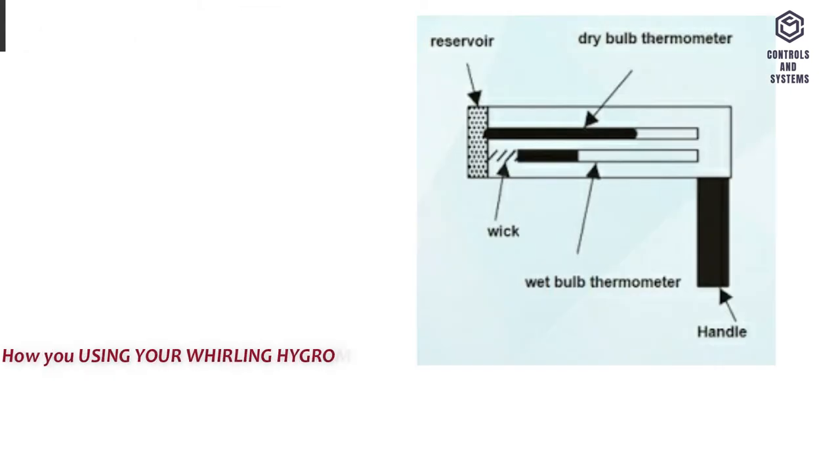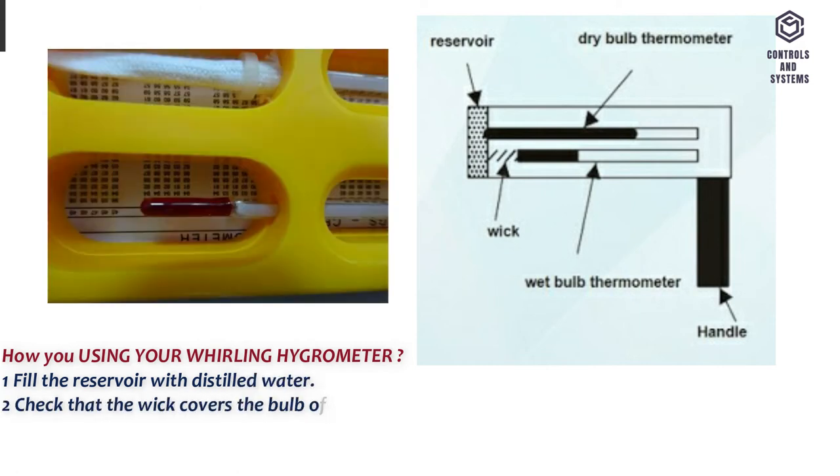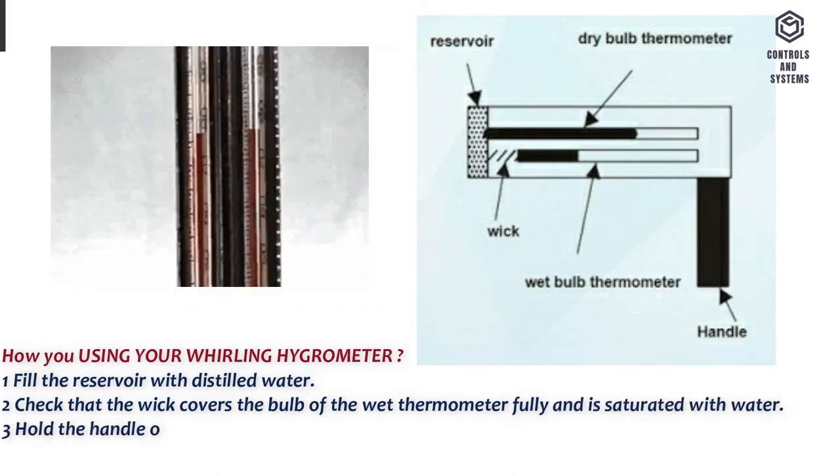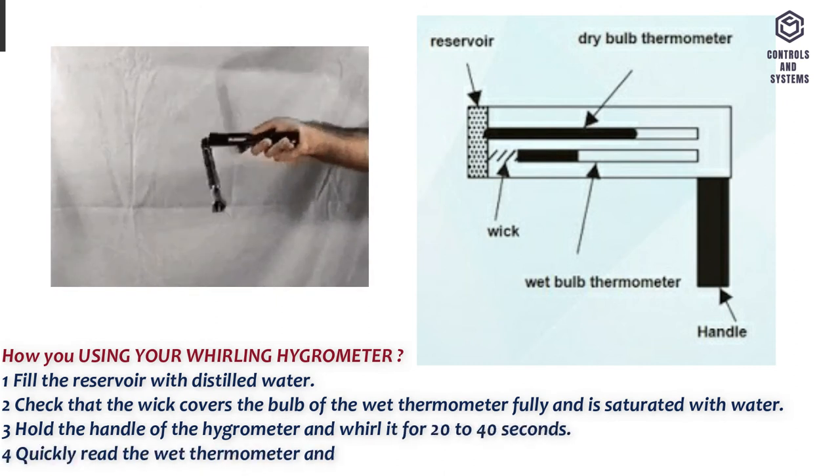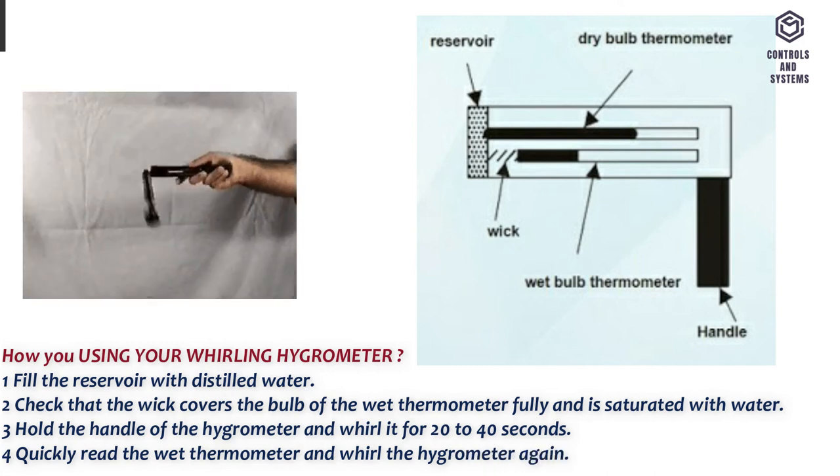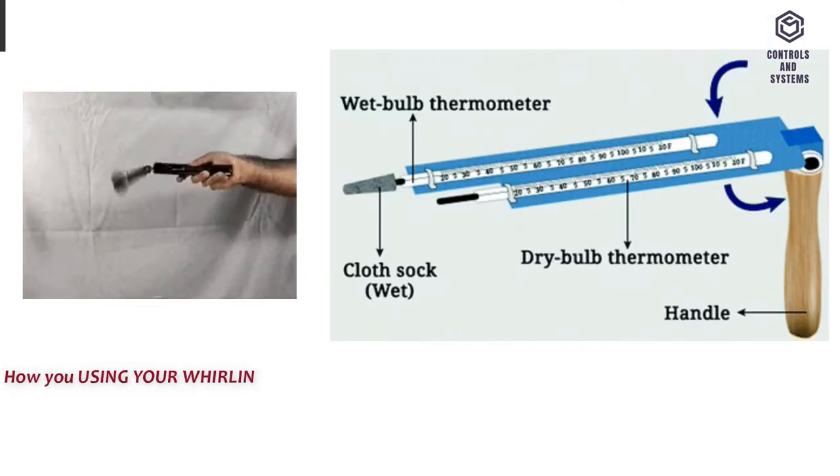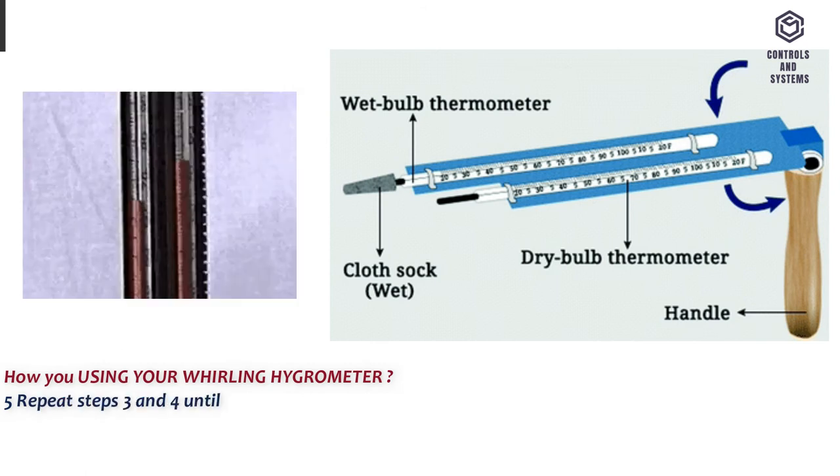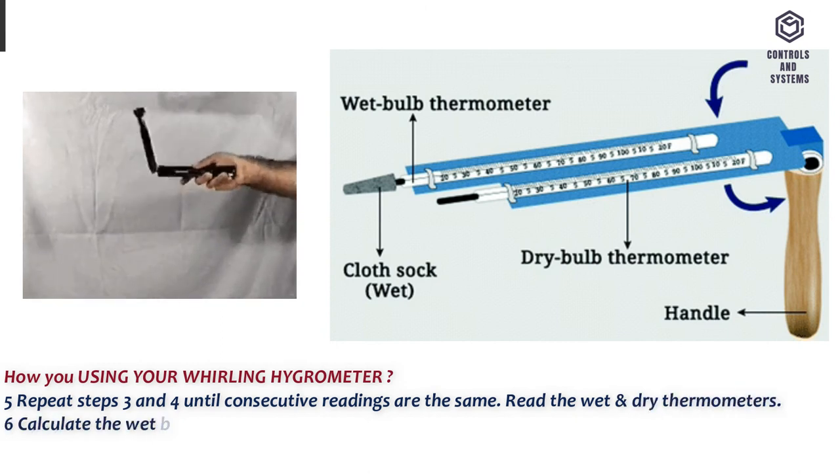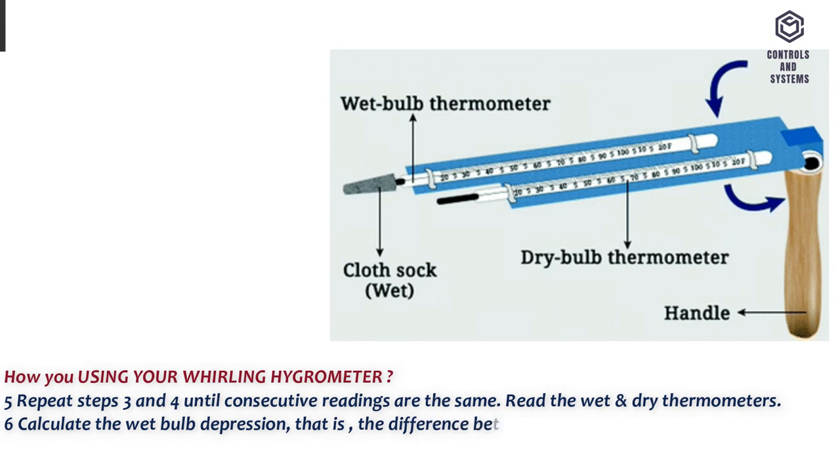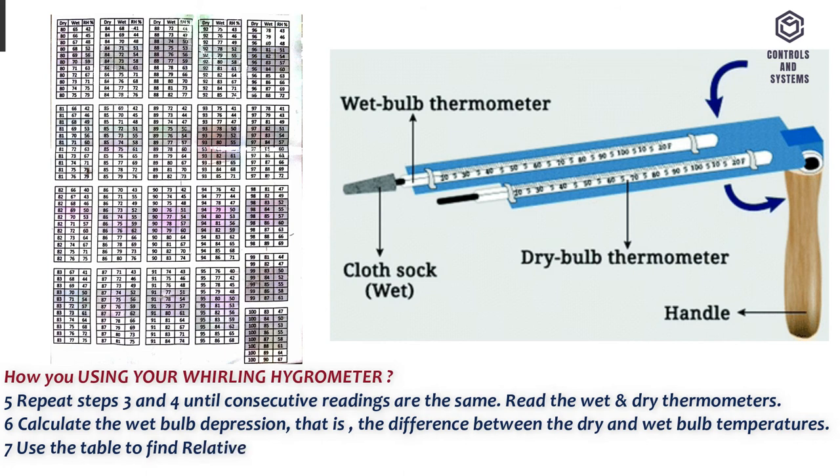How you use your whirling hygrometer. 1. Fill the reservoir with distilled water. 2. Check that the wick covers the bulb of the wet thermometer fully and is saturated with water. 3. Hold the handle of the hygrometer and whirl it for 20 to 40 seconds. 4. Quickly read the wet thermometer and whirl the hygrometer again. 5. Repeat steps 3 and 4 until consecutive readings are the same. Read the wet and dry thermometers. 6. Calculate the wet bulb depression, that is, the difference between the dry and wet bulb temperatures. 7. Use the table to find relative humidity.